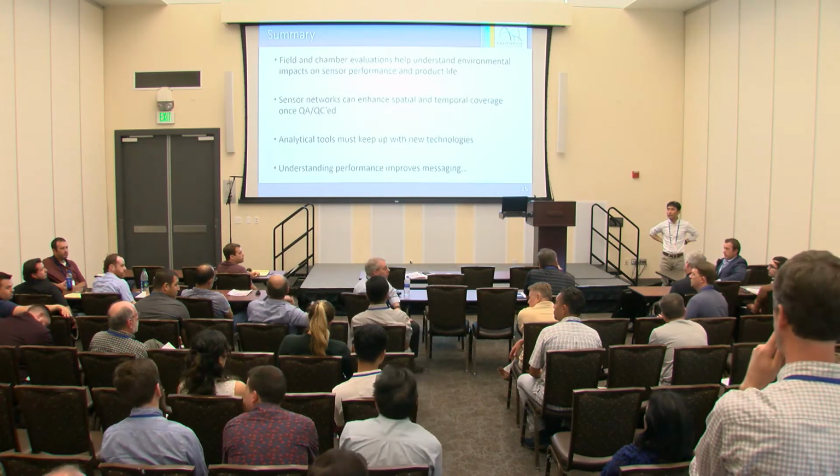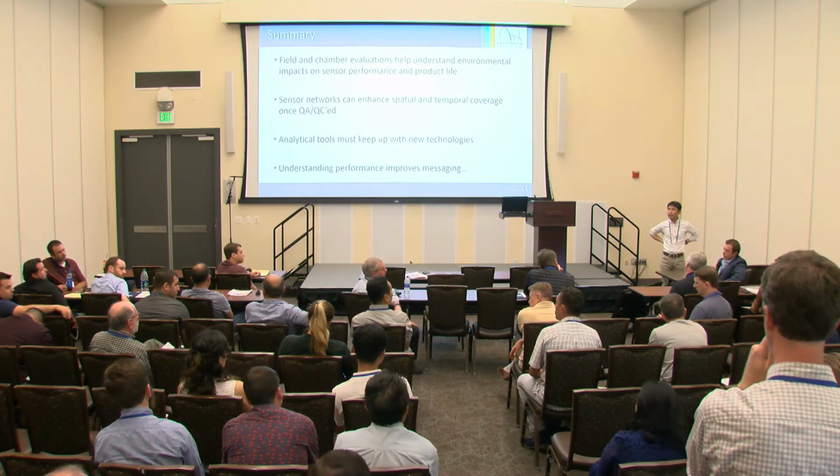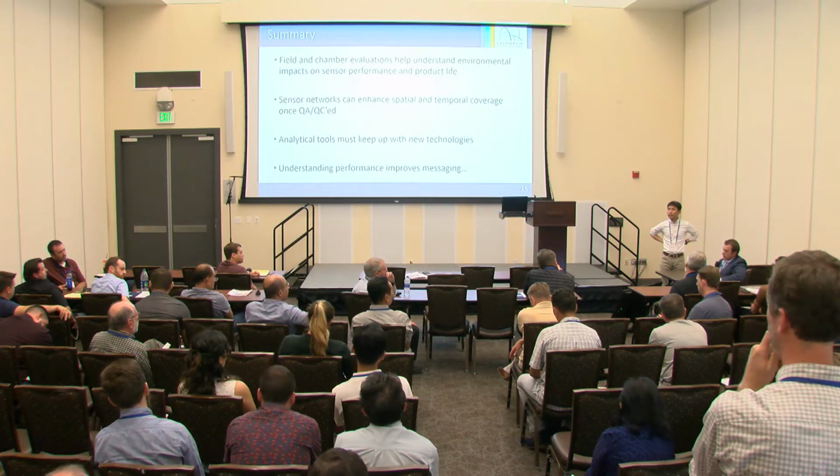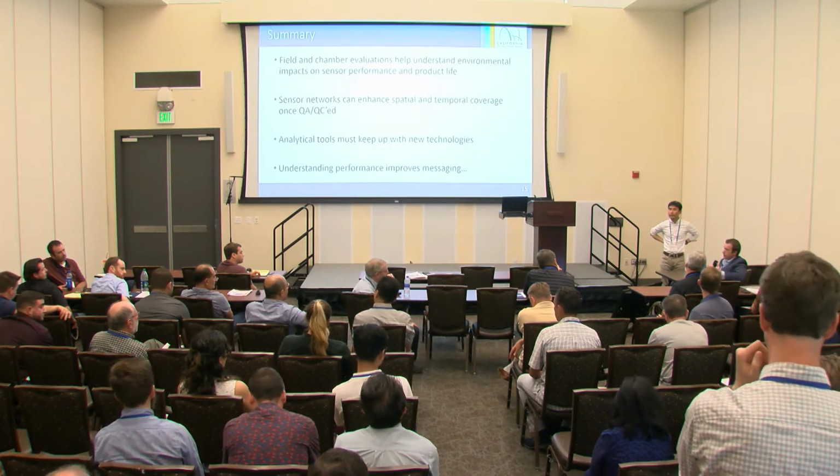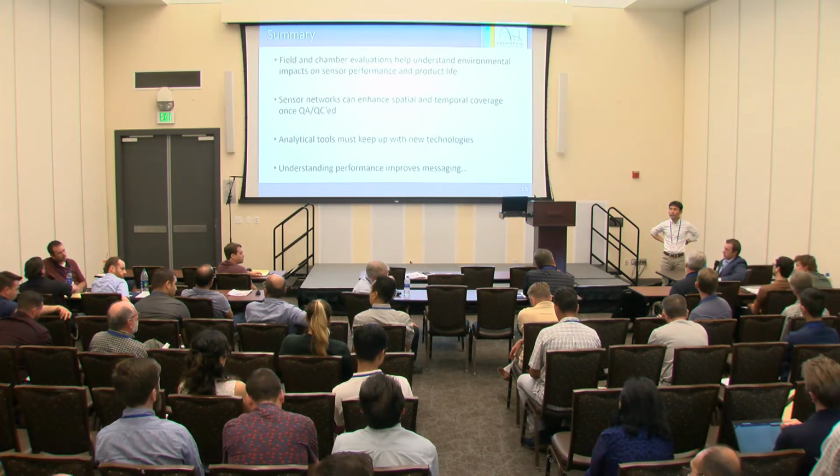Yeah, that's a good point as well, Mike. That's why we have the laboratory coupled with it, so we can get the full range of PM2.5 concentrations or gas concentrations that we might not see in the field, and also get a range of temperature and humidity that may not be present in the field evaluation.